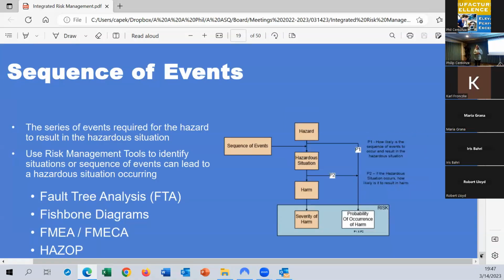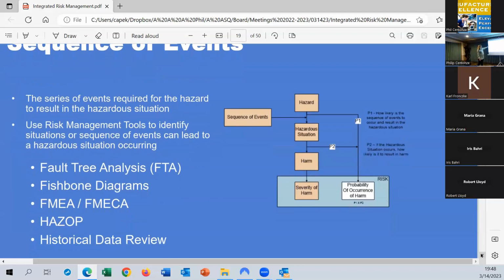Now, the sequence of events, this is probably a term that is not used in other industries, but in the medical device world, and probably in any industry, we want to understand the series of events that's required for the hazard to result in the hazardous situation. Sometimes there are multiple steps, right? In an FMEA, typically you look at a single failure. When you're doing risk analysis at the system level, you can say, well, if A and B and C happen, and that is a foreseeable thing, then I want to look at that, because I can mitigate at any step in that sequence, or at every step in that sequence. So typically, if we use FMEAs, fault trees, and fishbones, we can identify different items that would lead to that hazardous situation. That's how we identify our sequence of events.